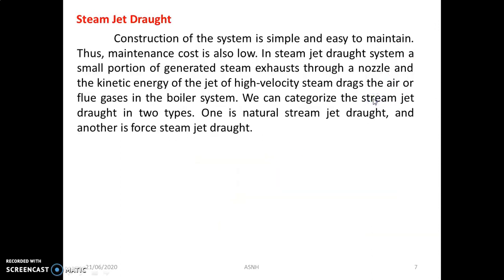The next important type is steam jet draft. It is a very easy technique. In the boiler, steam is produced and that steam is utilized in the combustion chamber for moving the flue gases toward the chimney area. The construction of the system is very simple and easy to maintain, so the maintenance cost is also less. In steam jet draft, a small portion of the generated steam exhausts through a nozzle, and the kinetic energy of that high-velocity steam jet drags the air or flue gases through the boiler system. Steam jet draft is categorized into two types: natural steam jet draft and forced steam jet draft.